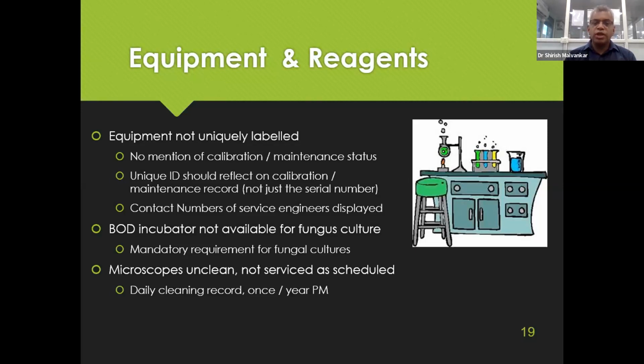So many a times when we cross-check the instrument calibration records or the preventive maintenance record, it has no mention of this unique label which you have generated internally, whereas the calibration record which has been coming from a calibration laboratory usually has the serial number, which is a good enough traceability of the instrument, but it would be advisable to also have that unique ID of your instrument on the label as well.